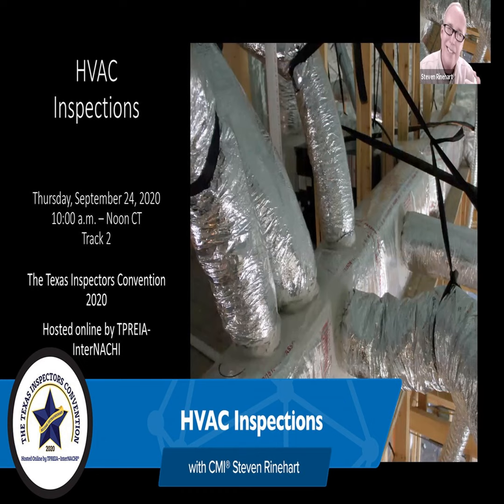That sucker collects lint and dirt for years. Nothing's worse than those old units where you have to pull the front cover off to get to the filter that's laying down at the bottom of the air handler, and they've lost the little clip that holds it down. They've got a brick or a 2x4 holding the filter down, or maybe nothing, so when it comes on, it lifts up and you get unfiltered air going into the unit.